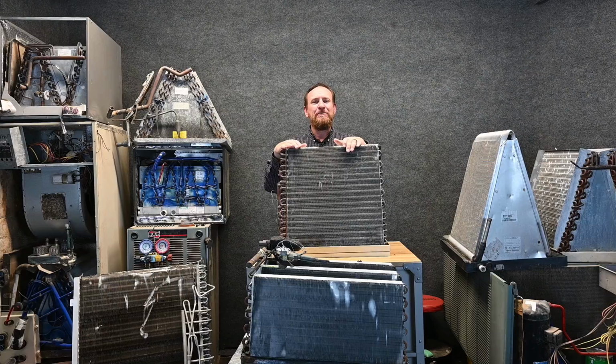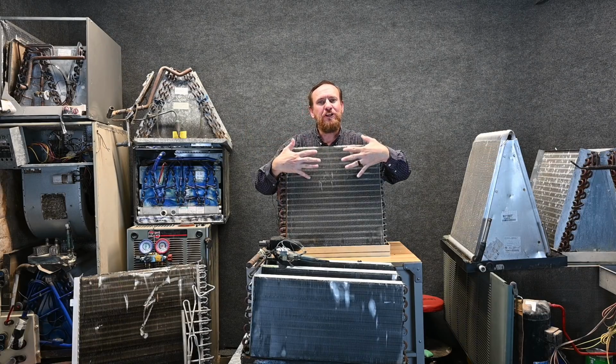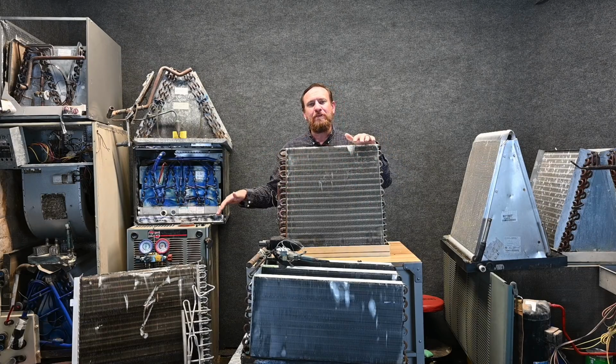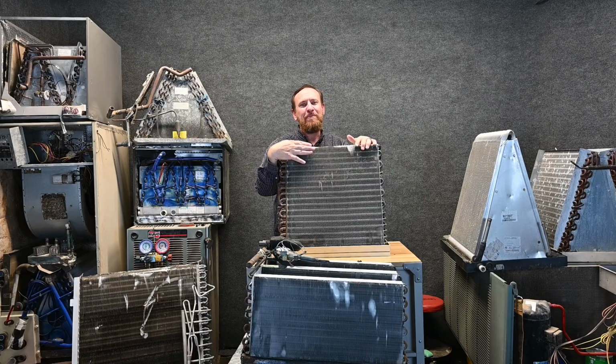When the AC system cycles off, we have something that's very important. If we live in a very moist climate, such as Florida, we want the blower to shut off with the AC because that moisture is going to stay on here and it's going to be dripping down into the drain pan and still going to be running off. The moisture doesn't just dry up right away.